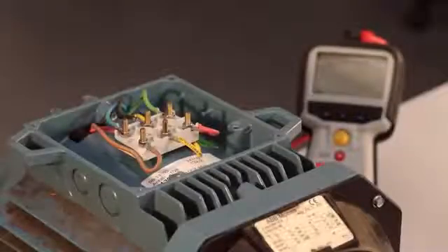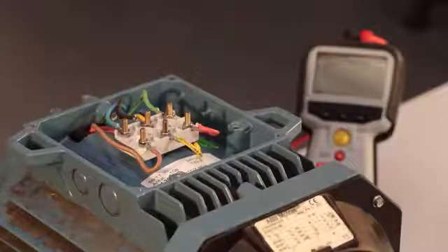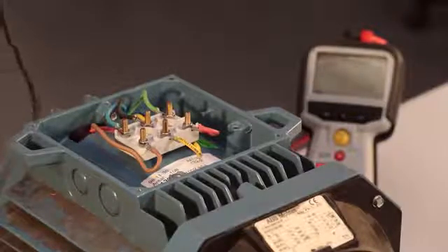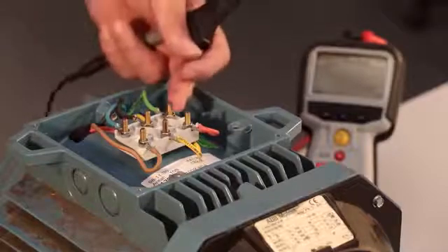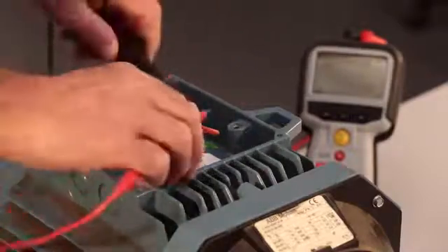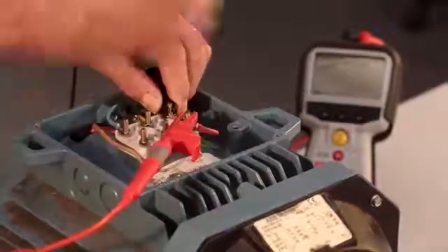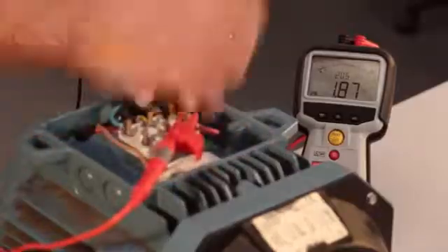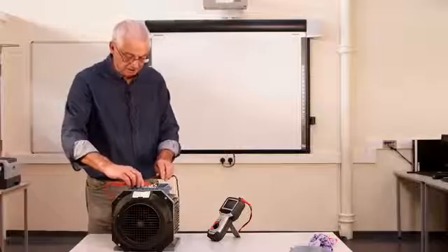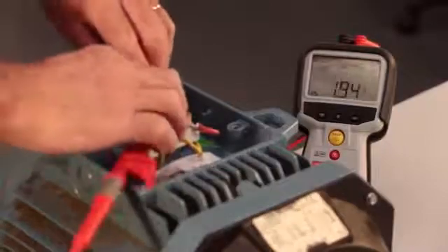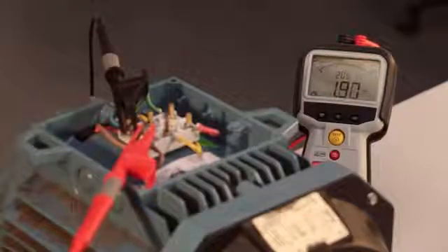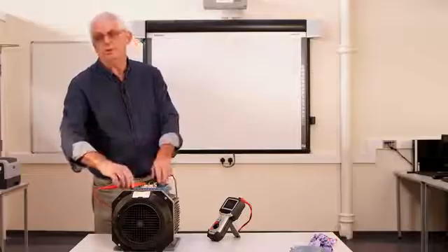Now I've connected the motor, just six individual terminals to start with. And really what I want to do just to be absolutely sure that I've not made a mistake is just check that I've got the correct ends. So on this terminal block this says W2, this says W1, so we know they should be together. So if I join them together I should get a reading and they're together. Now I'll go on to V1 and V2, again take a reading, close enough so I know I've got the right winding. Now to U1 and U2, again close enough so I know I've got the right winding.